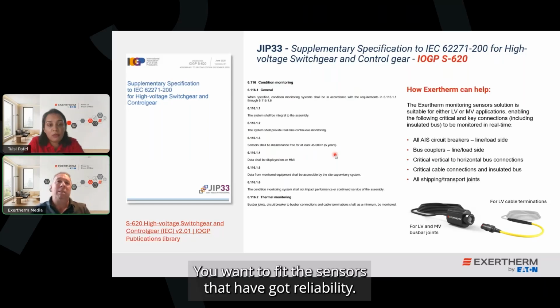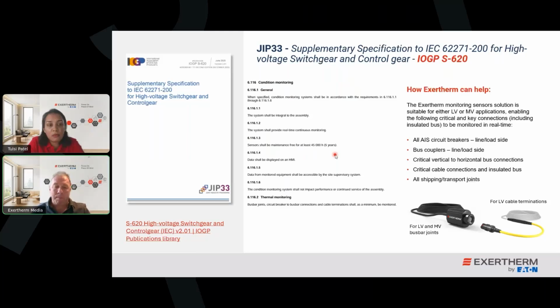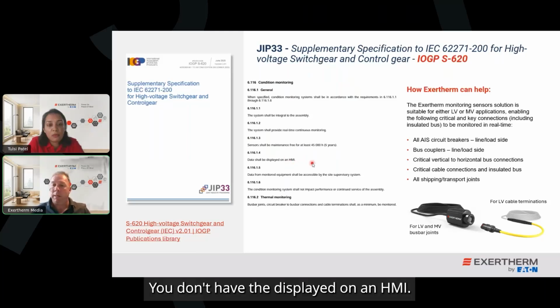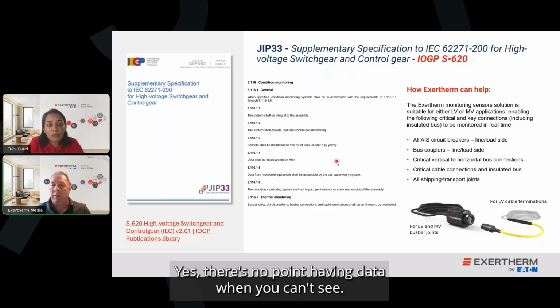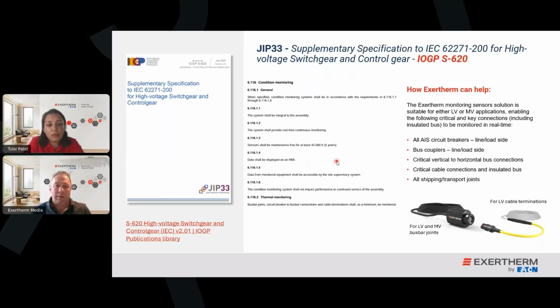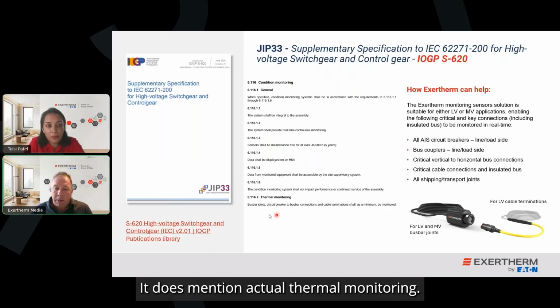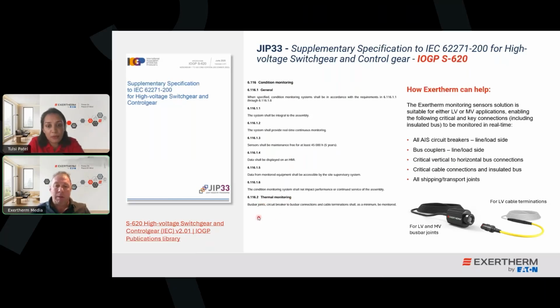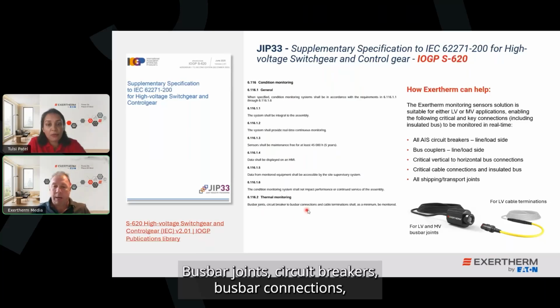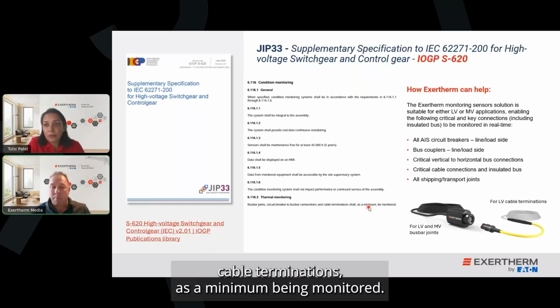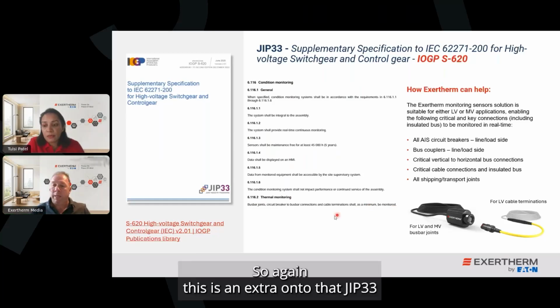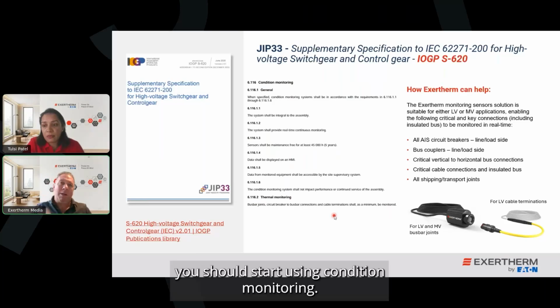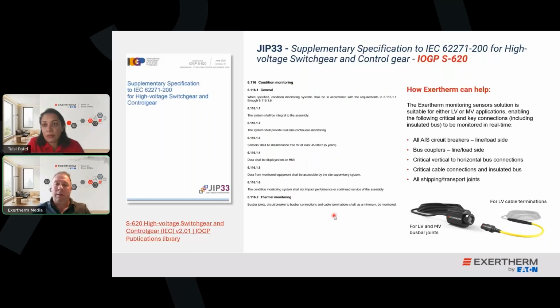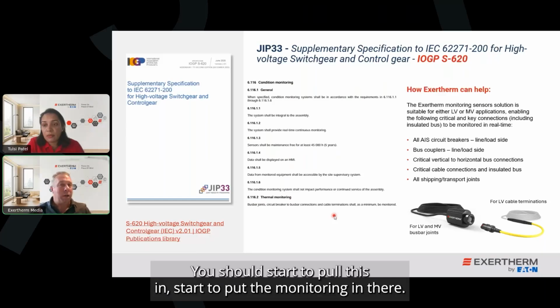You want to fit these sensors that have got reliability. Your data shall be displayed on an HMI. Yes, there's no point having data that you can't see. It does mention actual thermal monitoring, busbar joints, circuit breakers, busbar connections, cable terminations, as a minimum, be monitored. So again, this is an extra onto that JIP 33. You should start using condition monitoring. The standards are starting to push. You should start to put this in, start to put the monitoring in there.